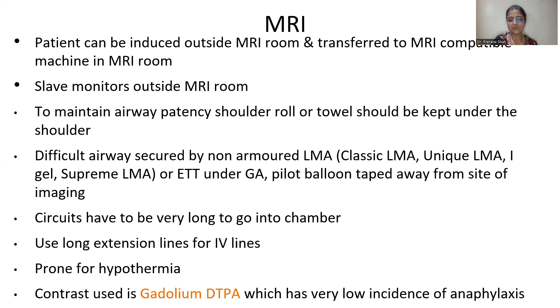Monitoring in the MRI suite, it is important that direct patient visualization is desirable, however, it may be difficult. MRI compatible monitors are used. The non-MRI compatible monitors should be placed outside the scan room, and cables can be passed through specially shielded holes in the walls. An MRI compatible anesthesia machine with piped anesthetic gases must be available, and non-compatible machines must be kept outside the line and bolted onto the floor.